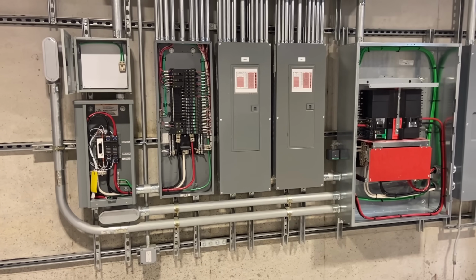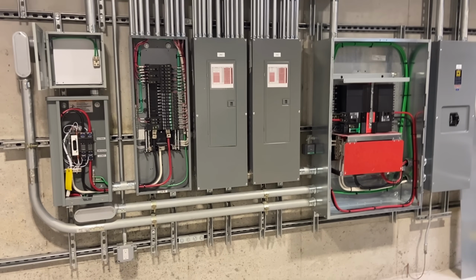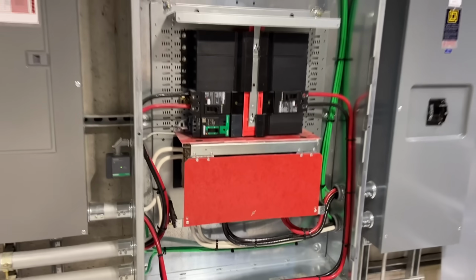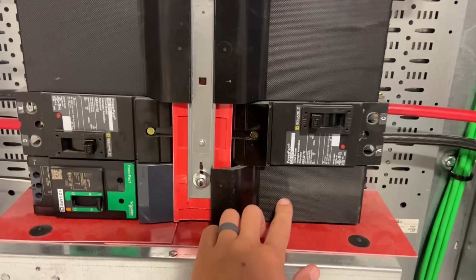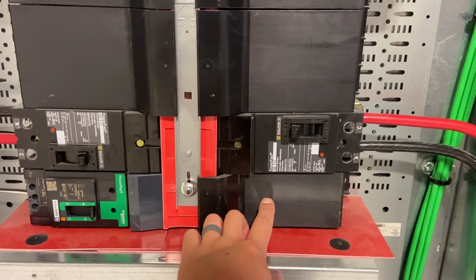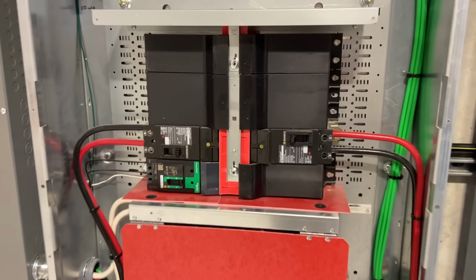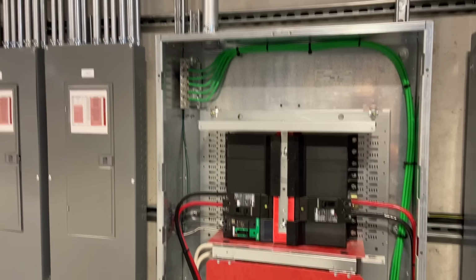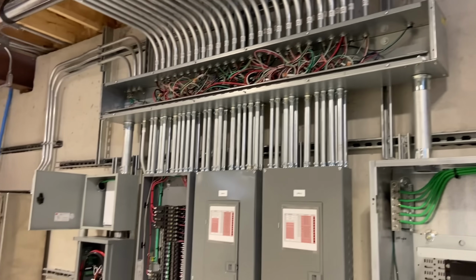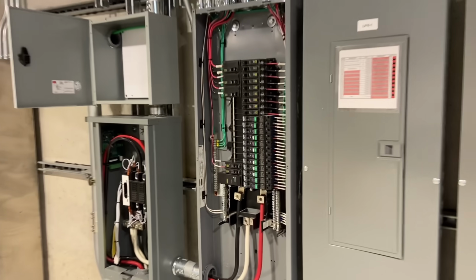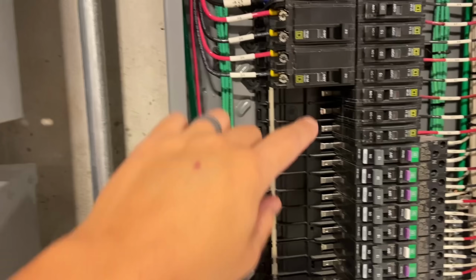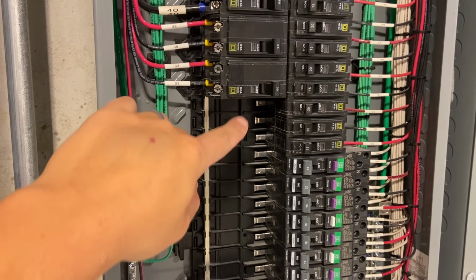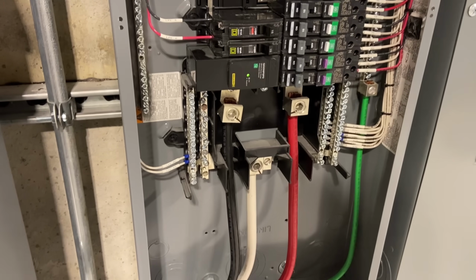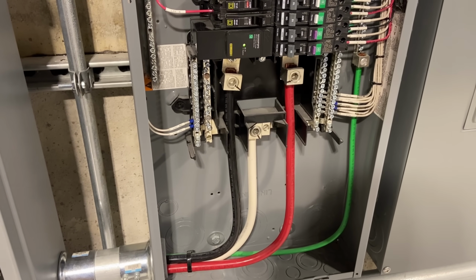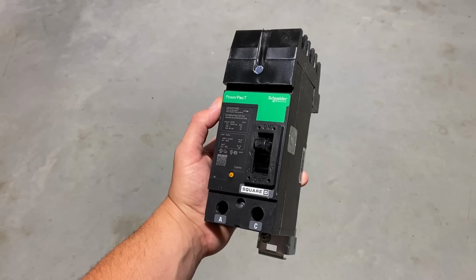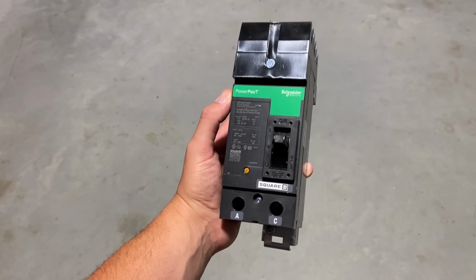So the first thing I really need to do is remove the old one, and right now everything is still powered up. I'm going to take this spot that was for the generator backfeed breaker and add a circuit breaker, using it as a temporary circuit breaker to feed that essential panel while I work on everything. So we're going to run a few wires up through the trough and backfeed a 100 amp breaker, or whatever I find, in that slot there. That way I can remove those wires on the bottom without having to get everything done in a time crunch. Once I remove those wires, I can just repower the panel and we're good to go.